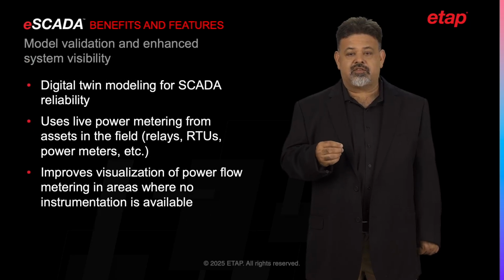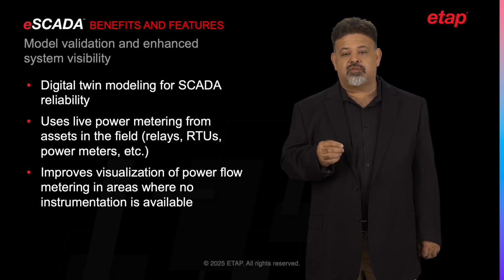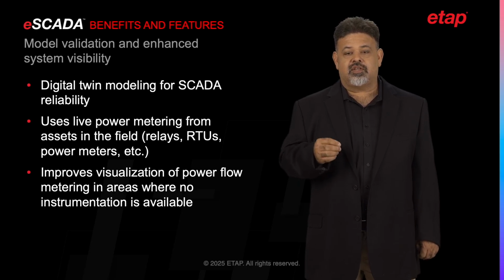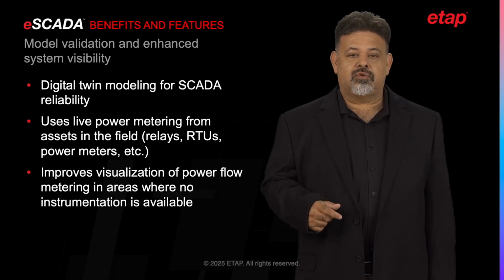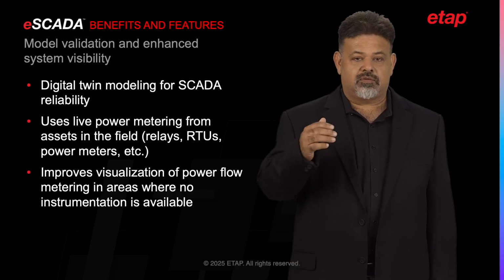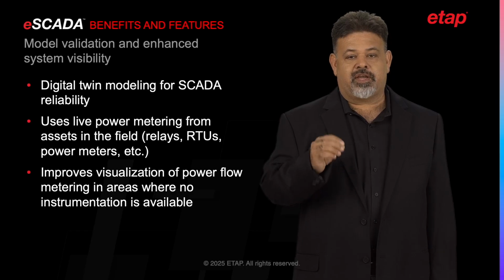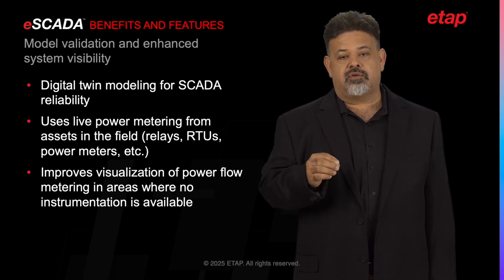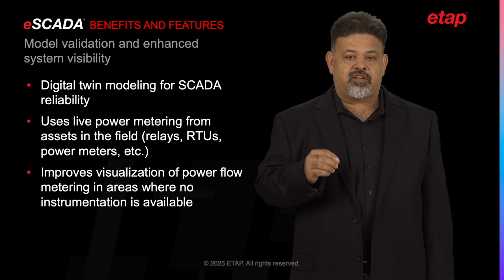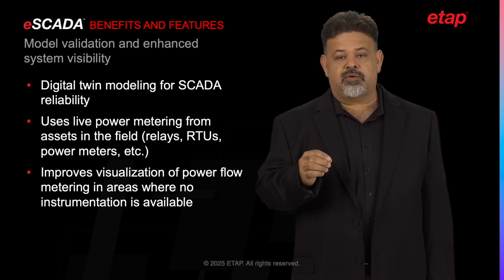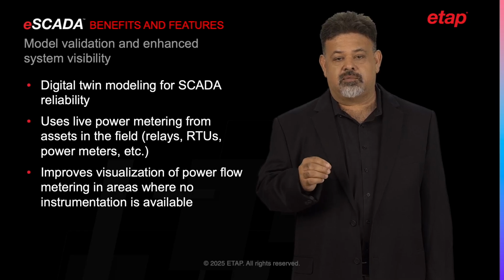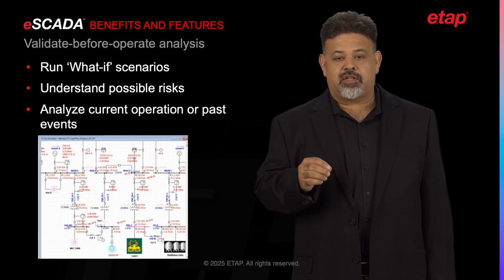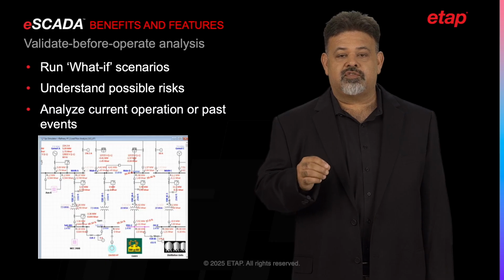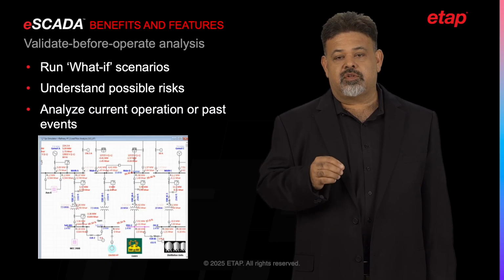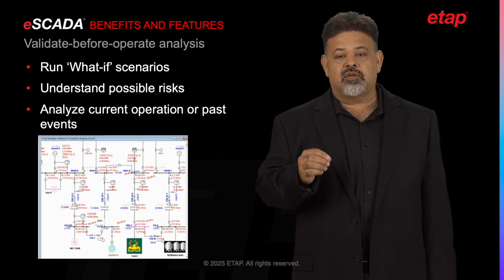Model validation and enhanced system visibility tools transform your existing digital twin model into a reliable eSCADA solution. The model validation tool uses an engineering perspective to validate the digital twin against live power and metering from assets in the field such as relays, RTUs, and power meters. The enhanced visibility increases the visualization of the power flow metering in areas where there is no instrumentation available. Validate before operate analysis allows engineers and operators to run what-if scenarios using ETAP power simulation modules and understand possible risk with current operations or events in the past.